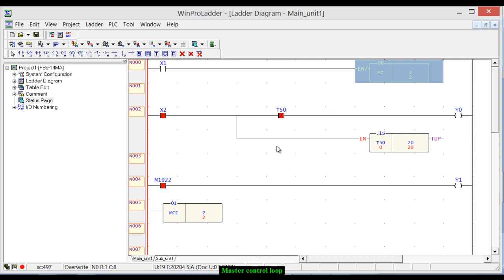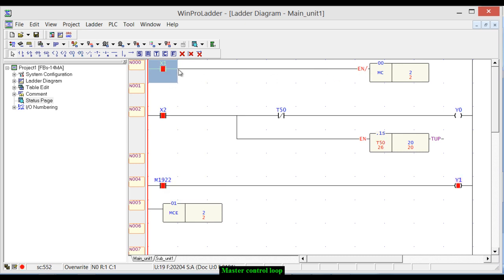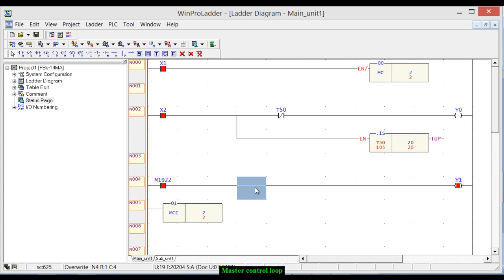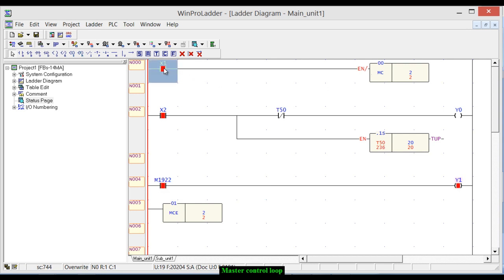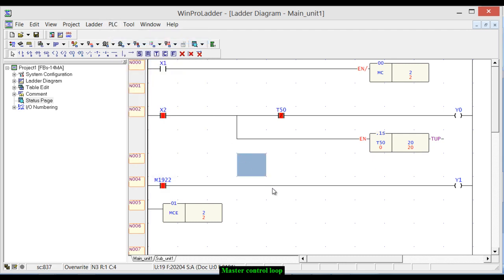When we make EN high — when enable equals 1 — the master control loop becomes inactive, meaning it no longer suppresses the instructions inside it. You can see the timer and the one-second clock pulse are now working normally, as if the master control loop instructions are not present. So the master control loop is active only when there is no input signal.